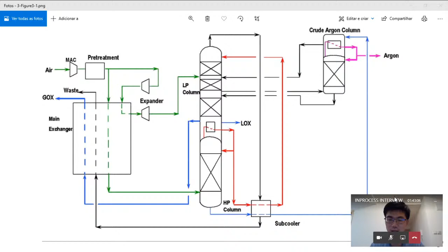Yes. How to say... actually it's a different phase. For design, it is the phase before, in front of the commissioning. You need design first, and then commissioning and startup or optimization. You need to take care and focus on the power calculation, focus on the pipe size when doing design, and focus on things like adding a valve, and how to control a valve or control compressors.